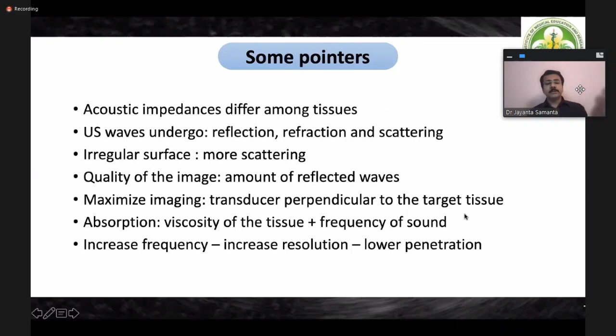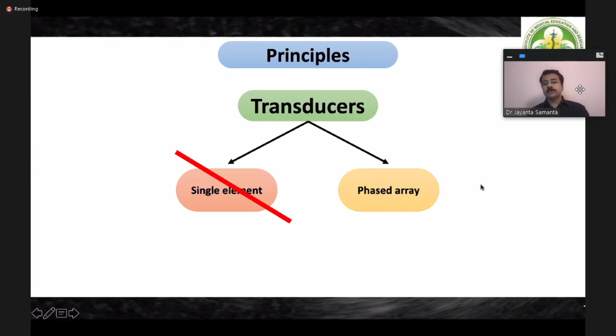So the principle is very simple. We use a transducer, which I had just described. Earlier, the transducer used to be a single element which had to be rotated by a rotor in order to obtain a 360-degree image. But these single element transducers are no longer available. Whatever we have in modern times are phased array transducers. That is the reason why you will always hear people talk about a radial array echoendoscope or a linear array echoendoscope. This array is basically the principle of the transducer that is being used. It's a phased array transducer.